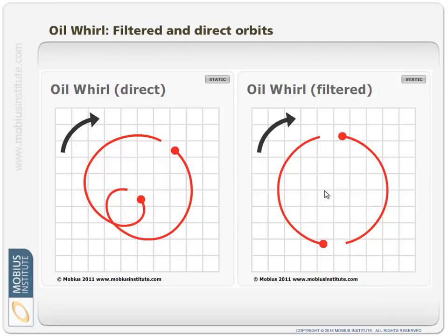We'd only ever see two dots at once, depending on how many rotations of the shaft we saw at any time. If we looked at the direct orbit, so the orbit that includes the 1x vibration and the 0.42x vibration, we get two dots, but we get this little inner loop. So the shaft has sort of made this motion. There's some 1x vibration there and some 0.4x.